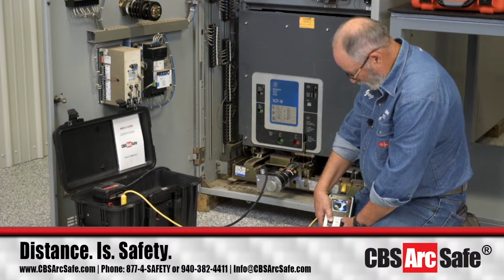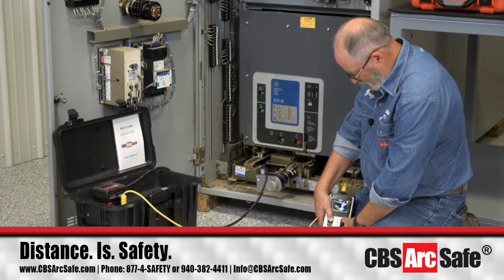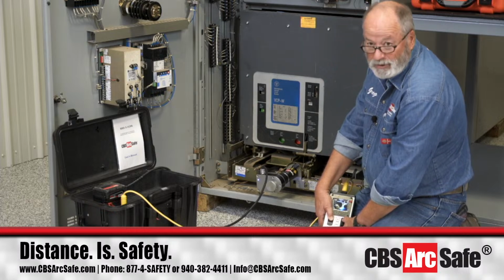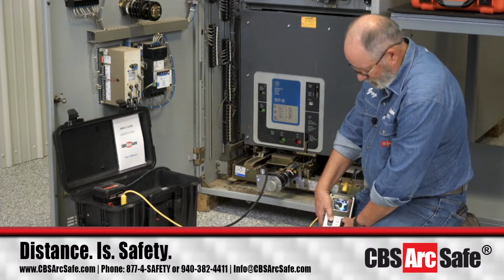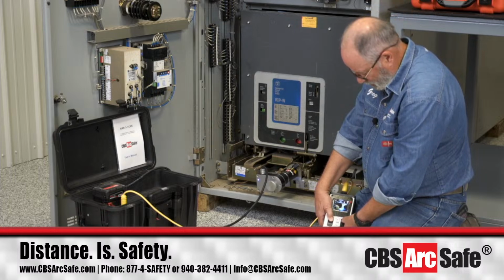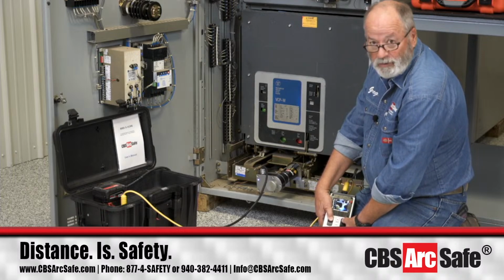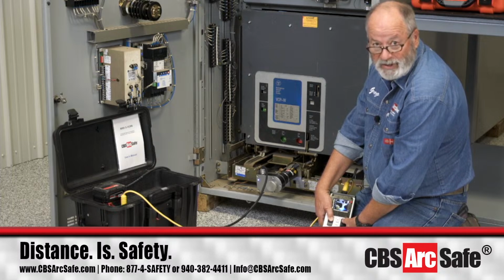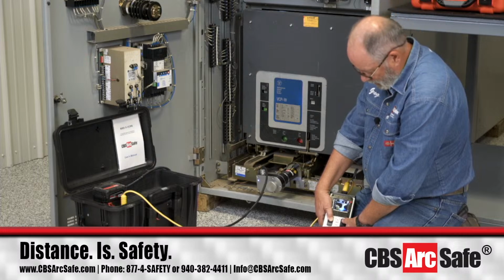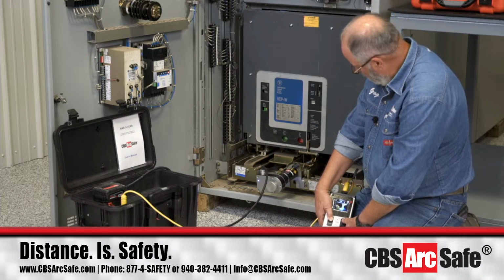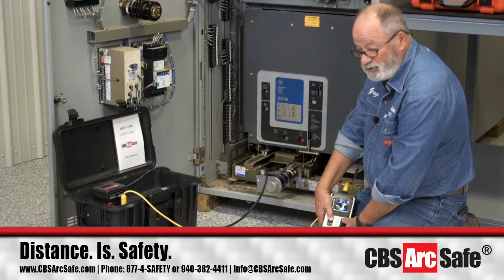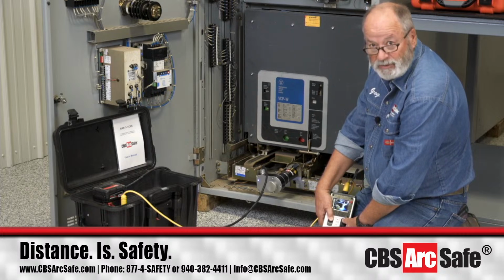In the lower right portion of the screen is the little indicator flag area to monitor when the breaker gets fully racked in. I can't let go of this right now to show you, but it's in the lower right-hand corner of the screen. When it gets all the way in, a little red flag will appear in that window, so our camera's keeping an eye on that. You just have to know that's what you're looking for in the system.